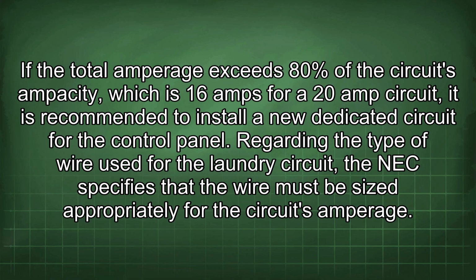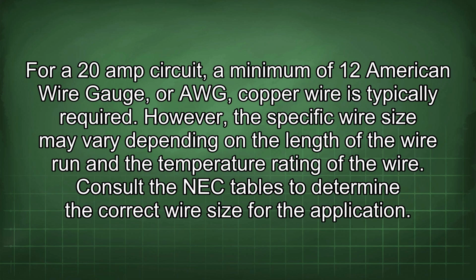Regarding the type of wire used for the laundry circuit, the NEC specifies that the wire must be sized appropriately for the circuit's amperage. For a 20 amp circuit, a minimum of 12 American wire gauge, or AWG, copper wire is typically required. However, the specific wire size may vary depending on the length of the wire run and the temperature rating of the wire. Consult the NEC tables to determine the correct wire size for the application.